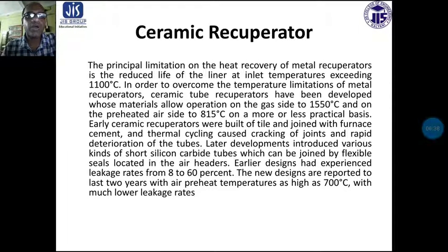In order to overcome the temperature limitations of metallic recuperators, ceramic tube recuperators have been developed. Ceramic materials allow operation on the gas side as high as 1550 degrees centigrade and on the preheated air side up to 815 degrees centigrade on a more or less practical basis.